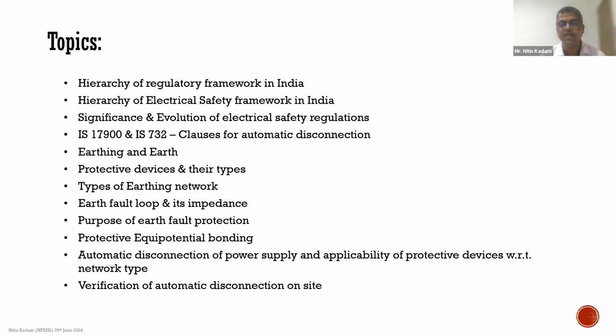their types, and as Mr. Gopakumar was just mentioning, the types of earthing networks, that is TN-S, TN-C-S, TT, IT, and so on. The earth fault loop, its impedance, the purpose of earth fault protection, protective equipotential bonding, and automatic disconnection of power supply. And what are the devices that are applicable with respect to the network types, and how do we verify this automatic disconnection on site is one of the important topics we will see today. I move on to the next slide.